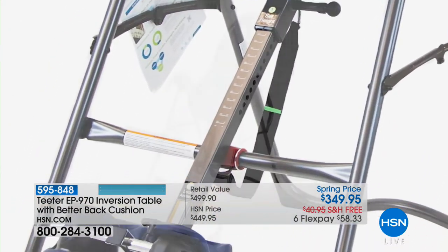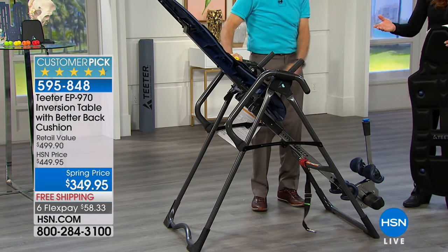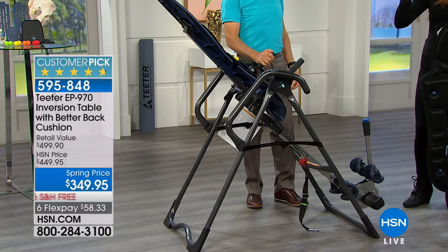When you cycle a table back and forth, the little support arms that carry your weight are loaded first one direction, then the other — that is what causes fatigue failure. See that vertical line on the right? That is the minimum requirement set by Underwriters Laboratory — 30,000 cycles. That long blue line on top — that's us; we went way past it. I did sit-ups on that table after 40,000 cycles. Look at the lookalikes: they don't use the right steel, they fatigue out — bent, broken, or torn metal. If I'm reading that correctly, every other table failed at some point. Dramatically.